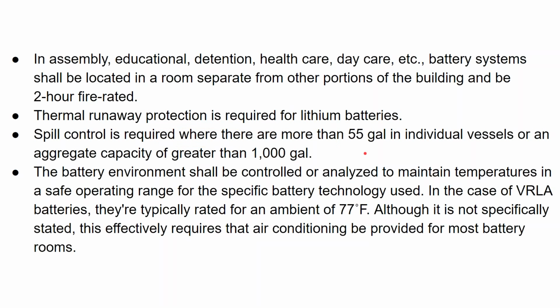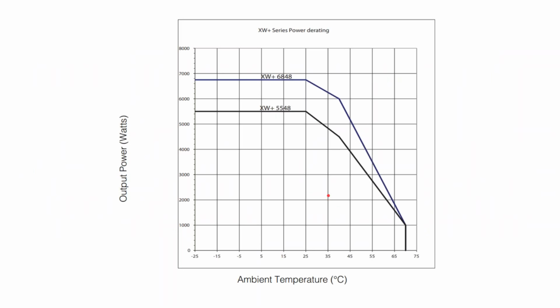There's a requirement that the batteries be controlled to maintain temperature. Flooded lead acid has a better temperature tolerance than lithium ion. You pretty much have to air condition a lithium ion battery. You don't have to air condition a lead acid battery, but it's still a good idea to have your whole battery inverter, battery system to be air conditioned. Here's why.